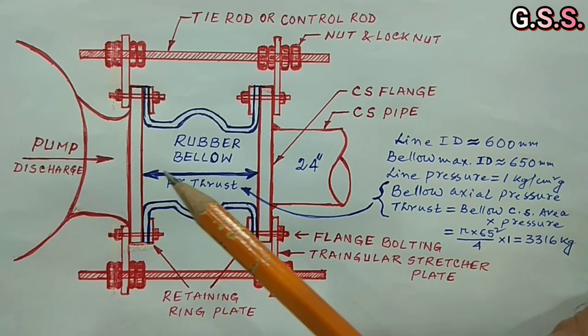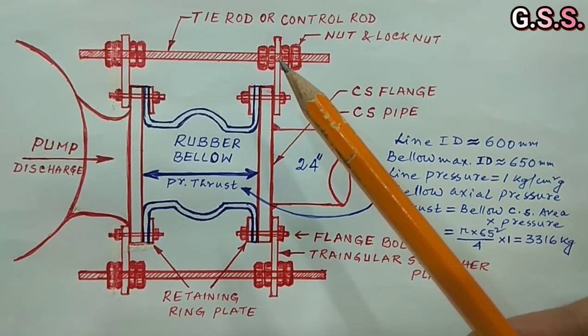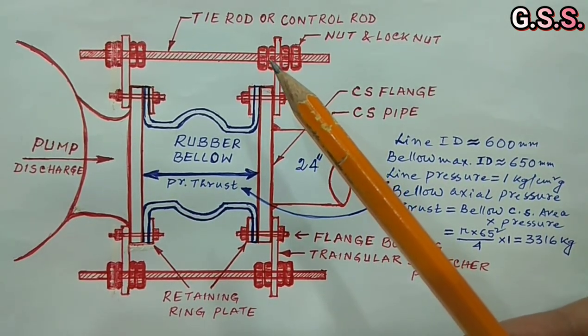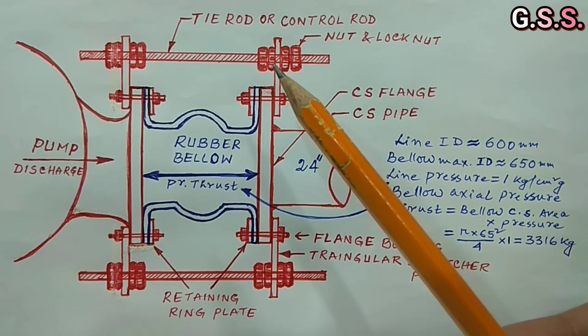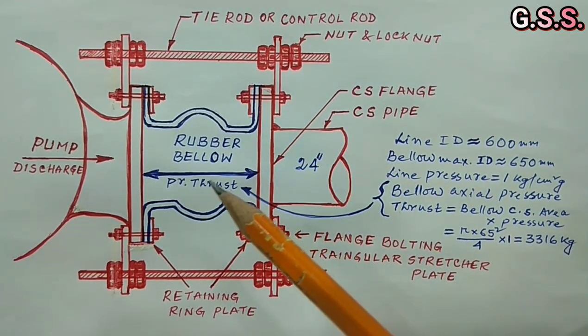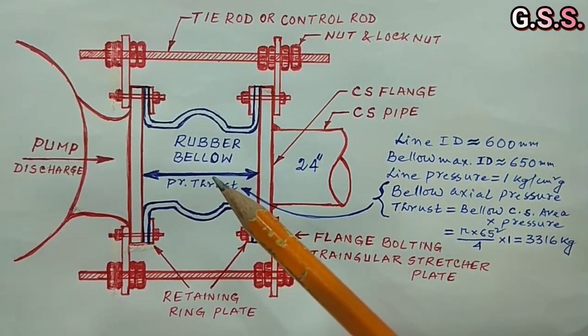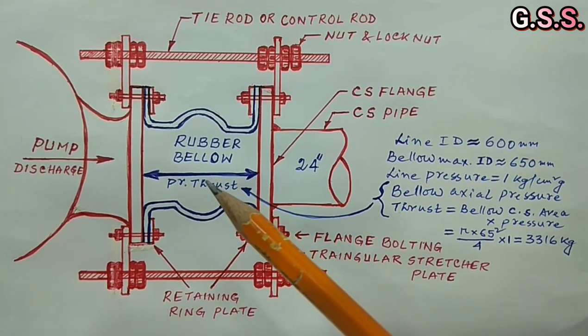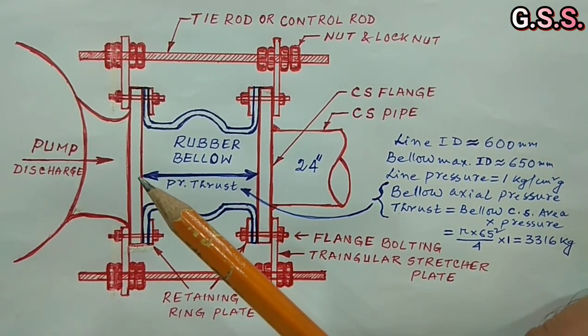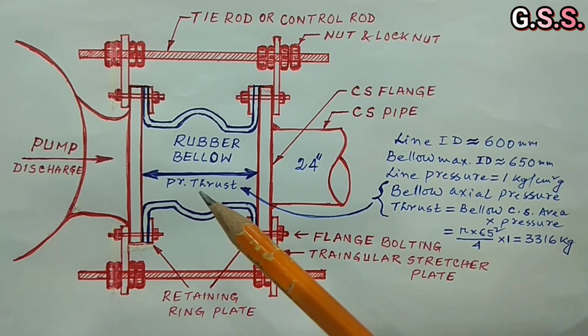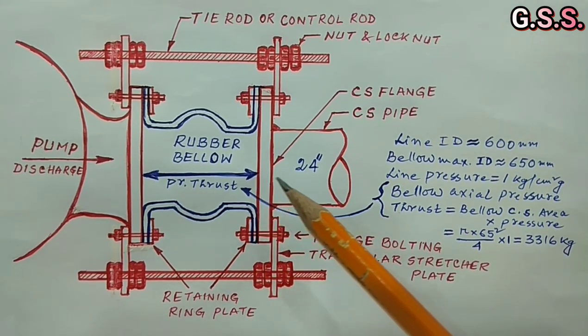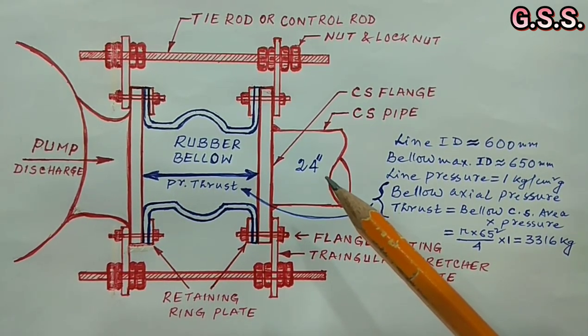But if we do not provide the tie rod or if we do not keep the tie rod nuts tight then this axial pressure thrust will be transmitted to the piping system and to the connected nozzle. Also bellow will be expanded axially and finally bellow may be torn off.